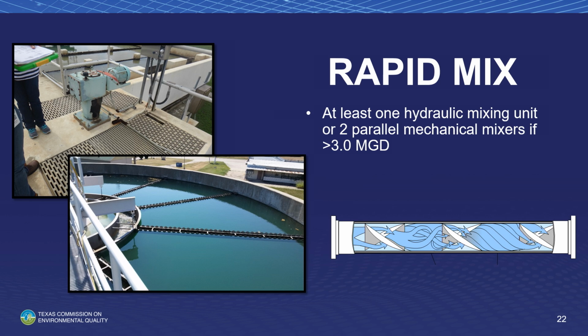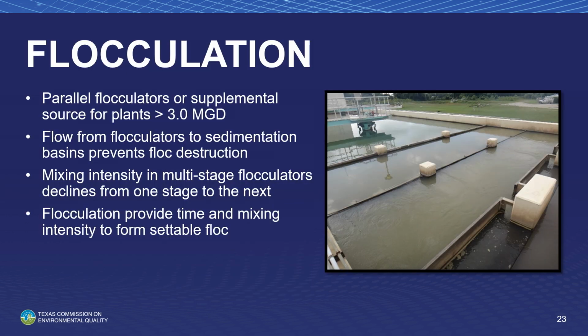Rapid mix is at least one hydraulic mixing unit or 2 parallel mechanical mixers if you produce more than 3 MGD. Here are pictures of different versions of rapid mix that you can see. Sometimes it's just as simple as having an inline static mixer. Flocculation, so parallel flocculators or supplemental sources for plants that are greater than 3 MGD. Flow from flocculators to settling basins.